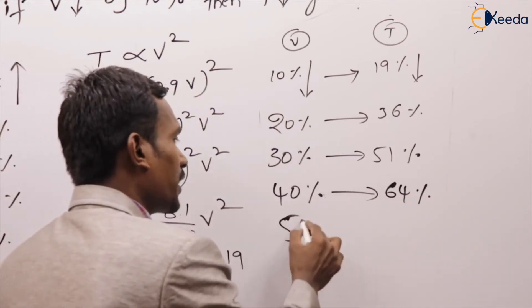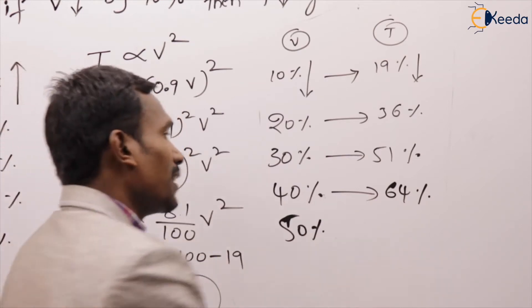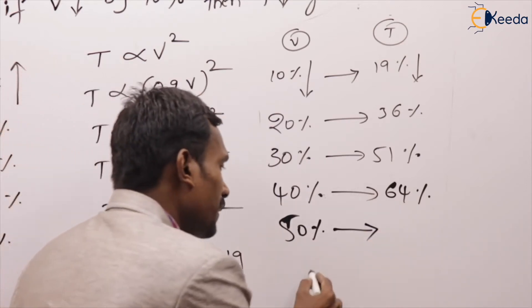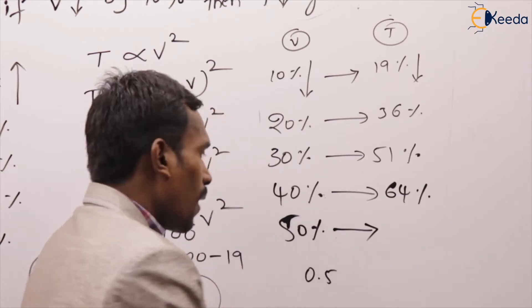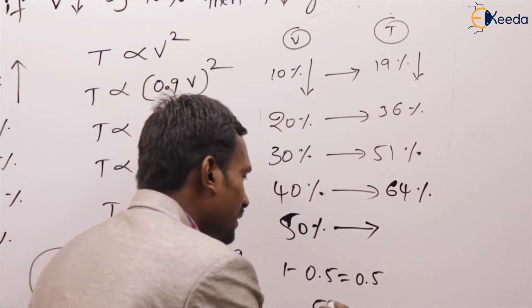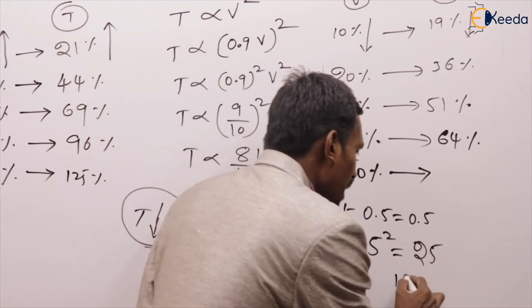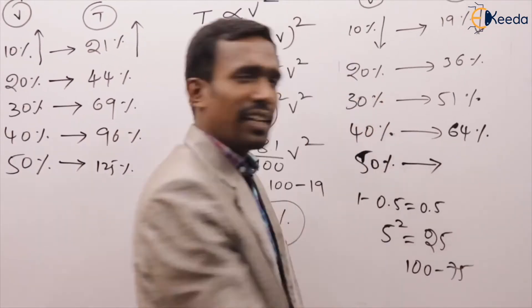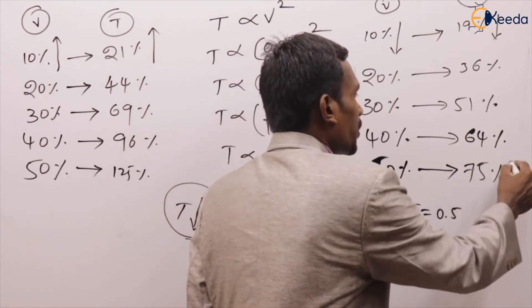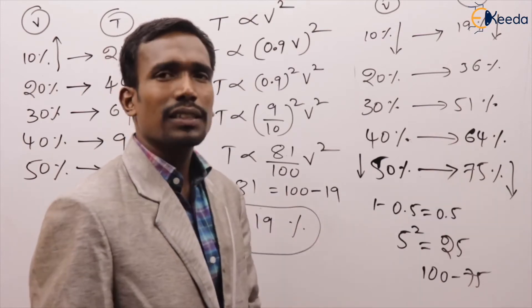If voltage reduced by 50%, the factor is 0.5, so 0.5 squared = 0.25, meaning 5 squared = 25, which is 100 minus 75. So torque reduced by 75%.